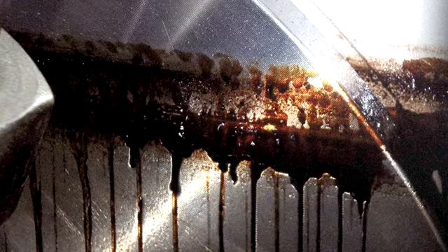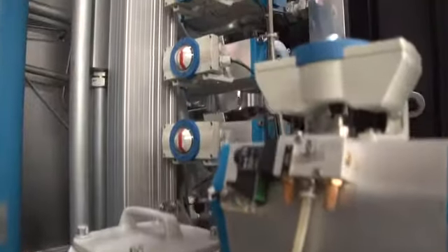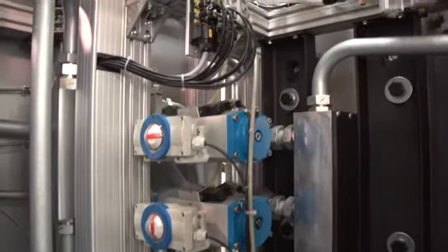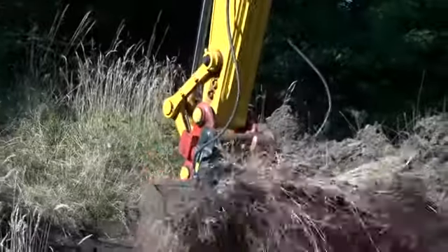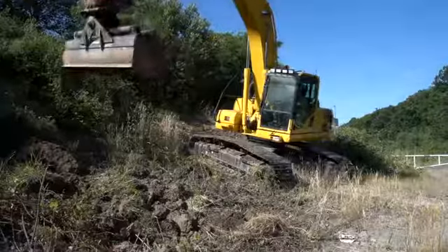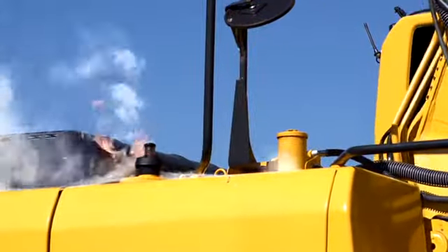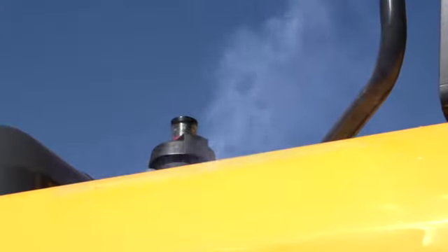The electrostatic discharge also creates oil sludge. The sludge can block filters or collect in valves and bearings, making them much less effective. Electronic components can also be severely impaired or destroyed. In certain cases, discharge can even cause explosions in the hydraulic tank. This can cause severe personal injury in addition to technical failure and downtime.